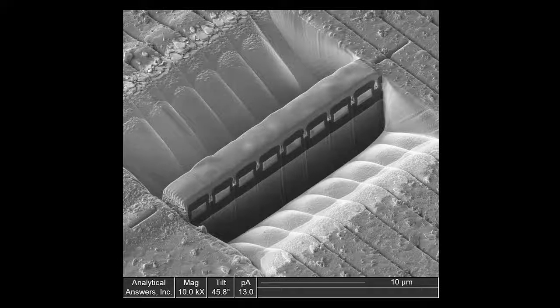One of the more popular uses for focused ion beam milling is to prepare TEM samples or STEM samples. And this is where you need to make a sample that's thin enough that electrons can actually pass through it, and that allows you to do much higher magnification imaging than you can do in a standard SEM, and it allows you to do elemental analysis on a much smaller scale than you can do in a normal SEM, where you're typically limited to look at microns. With a STEM thin sample, you can actually look at features a few tens of nanometers across.